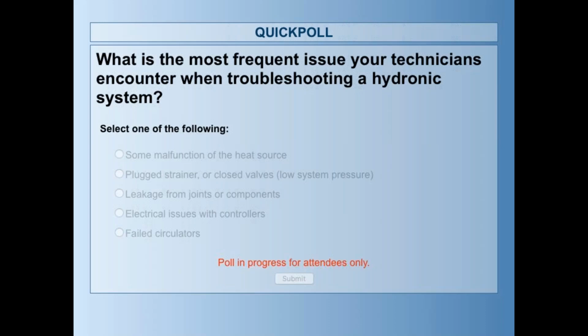Yeah, the short answer is if you double the pump speed, you will not get double the flow rate. Remember, that system curve goes steeper and steeper as you go to higher flow rates. And a good analogy to it, I think, was with cars. If we had a car with a 100 horsepower engine and we can go 100 miles per hour with that car with the throttle wide open, and let's say you wanted to go 200 miles per hour, like NASCAR speed, could you do it by taking the 100 horsepower up to 200 horsepower? And if you follow NASCAR, you know the answer to that is absolutely not. Those cars are running more like 800 horsepower. So no, you cannot double the BTUs per hour or double the flow rate by increasing the pump speed.